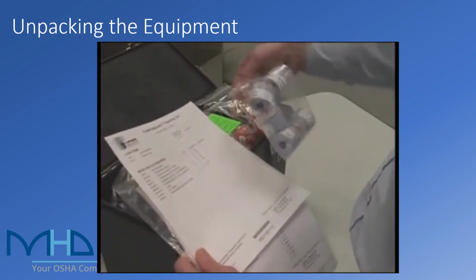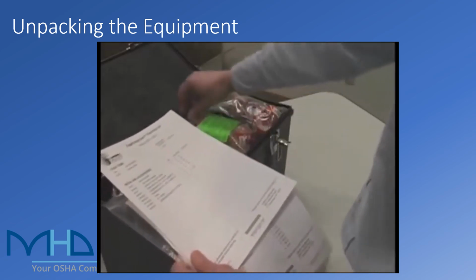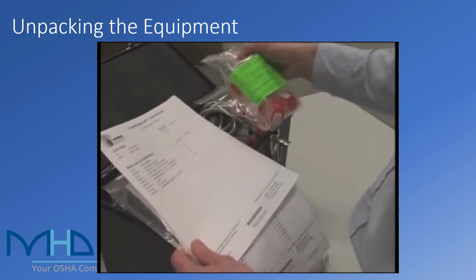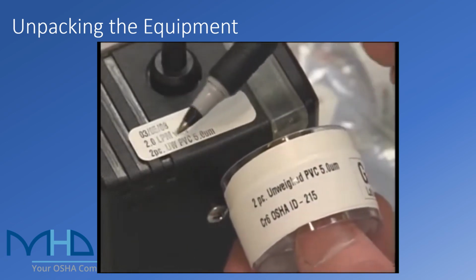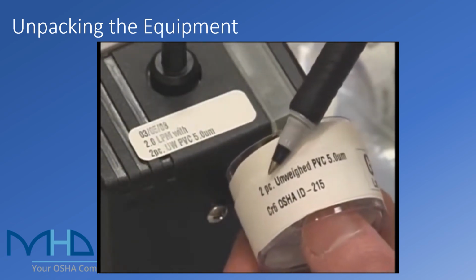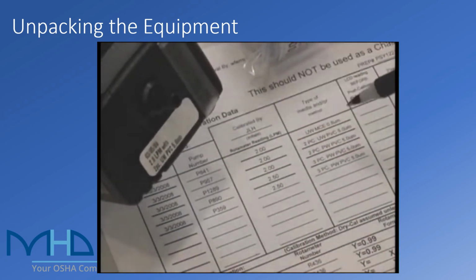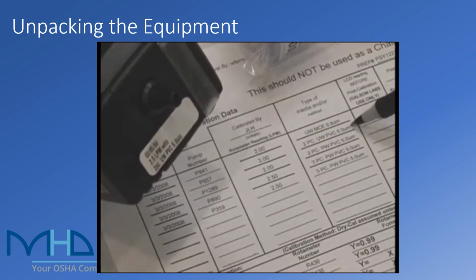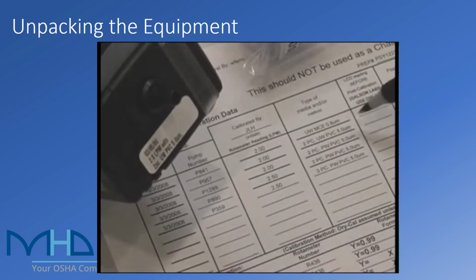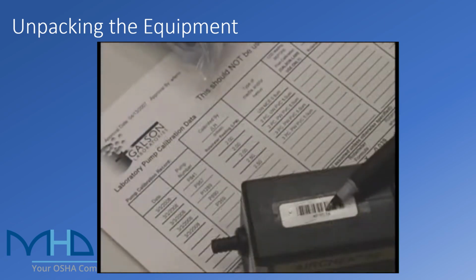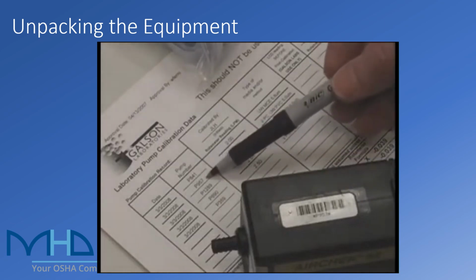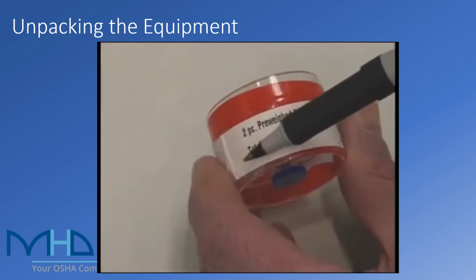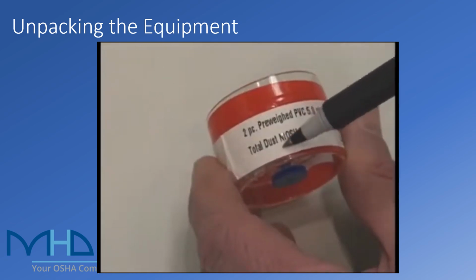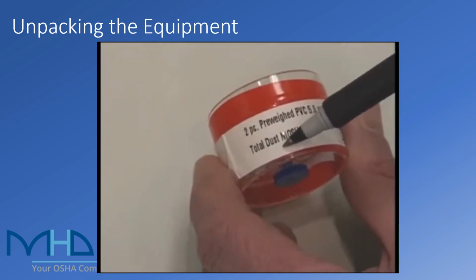Confirm you have all media and materials requested for your sampling event using the packing list provided. Make sure you keep pumps and their corresponding media together, and you know which media is used for each method. This can be done by matching the pump calibration sheet information with the label on the pumps themselves to see what pumps are to be used with what media. The labels on the pumps should match the information on the pump calibration sheets. That is, all pumps will have a label with the flow rate and type of media to be used. The media will be labeled as to what it is used for, so verify that you know what filters are to be used for what method.